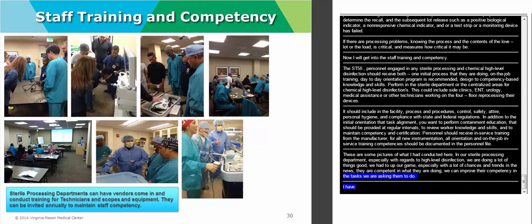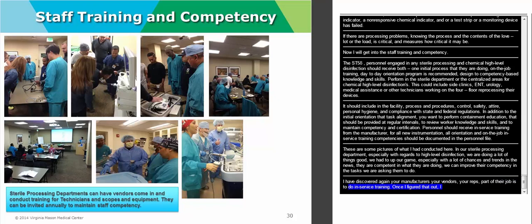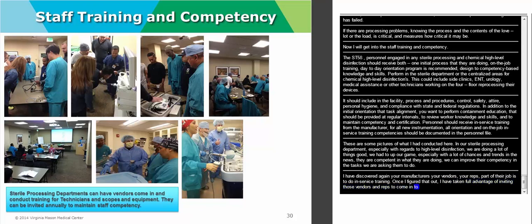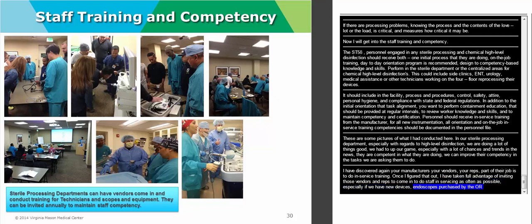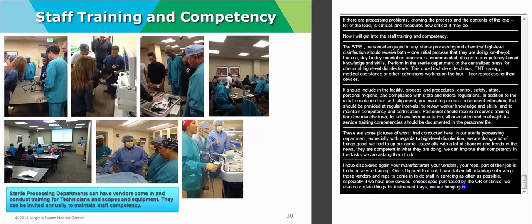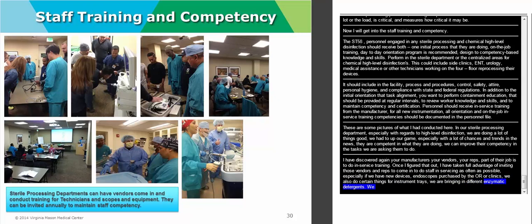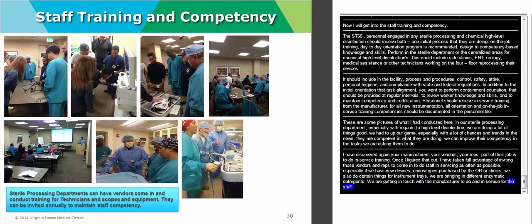So I have discovered, again, that your manufacturers, your vendors, your reps, part of their job is to do in-service training. And once I figured that out, I have taken full advantage of inviting those vendors and reps to come in and do staff in-servicing as often as possible. Especially if we have any new devices, new endoscopes purchased by the OR or clinics. We also do certain things for instrument trays. We're also bringing in a different enzymatic detergent, so I'm getting in touch with the manufacturer of that detergent to come in and do an in-service for the staff on contact time and the like, even for a new enzymatic detergent, just so that the staff knows what it is they're handling and how to use it.